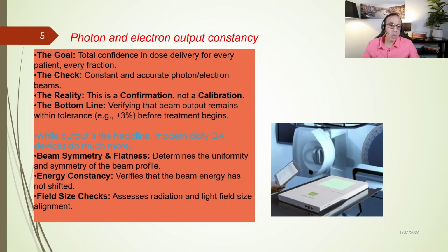Beyond just the dose output, modern daily check devices allow us to verify several other critical parameters simultaneously. Beam symmetry and flatness is one of them. We ensure the radiation beam is uniform across the entire field, so the dose is distributed evenly. Energy constancy: we verify that the beam penetrating power has not shifted, ensuring the dose reaches the intended depth. And we check the field size. We confirm that the light field and the radiation field are perfectly aligned.